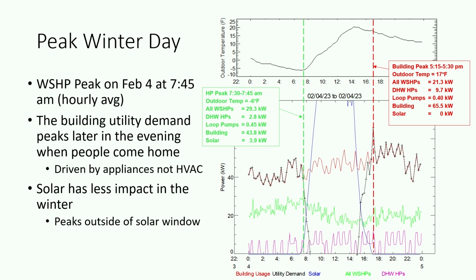So here is the point. At that moment when it's -6, the peak demand on the water source heat pumps was 29 kW. The DHW heat pumps weren't running at that moment. The building was 43 kW.